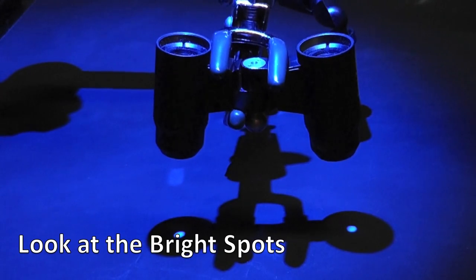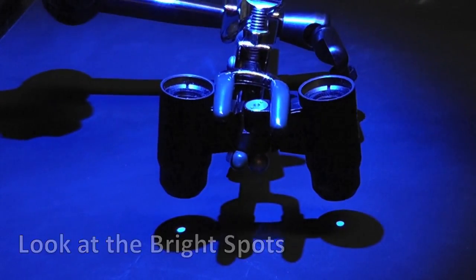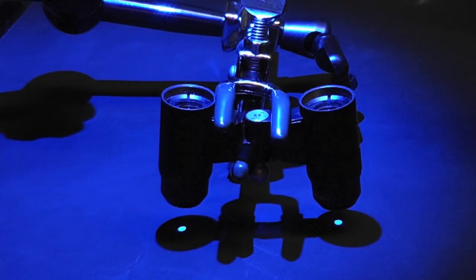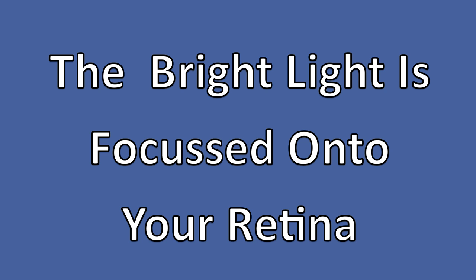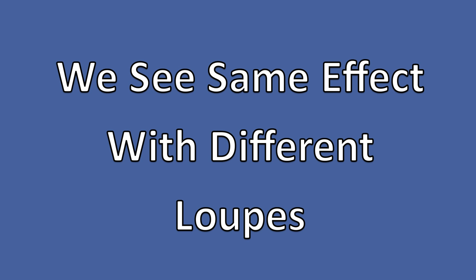As a practical demonstration, look at what happens when you look at a dental curing light through one of these loupes. See how the bright blue light is focused onto a spot full of wavelengths around 440 nanometers — and remember, this is focused right onto your retina. We see the same effect with a different pair of loupes, except that this time the result is a larger, less intense spot.